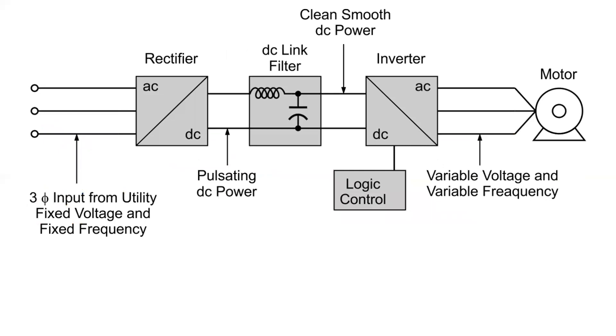Looking at a more detailed diagram, we can see fixed voltage and fixed frequency three-phase from the utility entering a rectifier. The rectifier won't produce perfect DC — it's more of a pulsating DC. A filter consisting of an inductor and a capacitor smooths the DC into a clean smooth DC voltage, which is then sent through an inverter that converts the DC to AC voltage going to the motor at variable voltage and variable frequency.